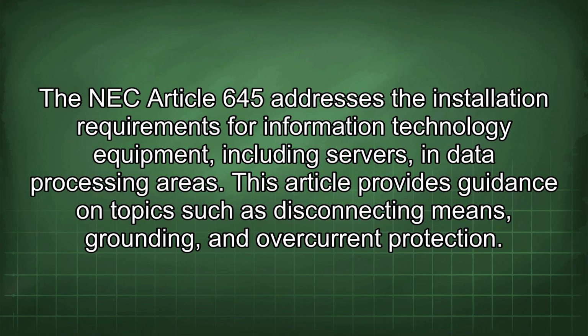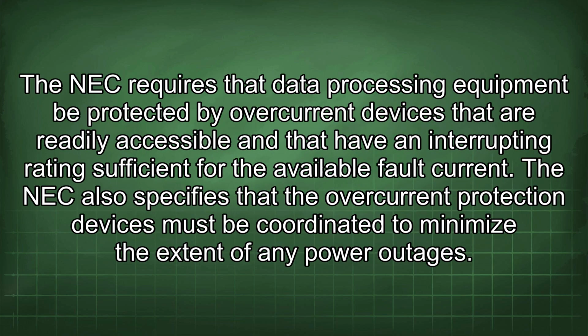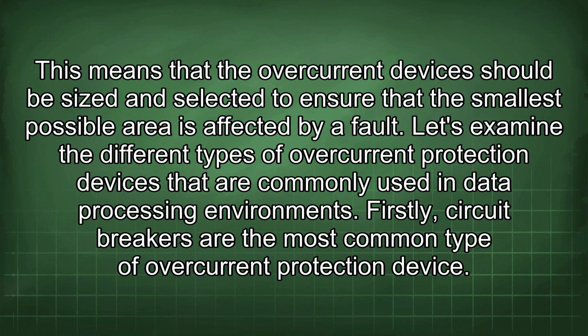This article provides guidance on topics such as disconnecting means, grounding, and overcurrent protection. The NEC requires that data processing equipment be protected by overcurrent devices that are readily accessible and that have an interrupting rating sufficient for the available fault current. The NEC also specifies that the overcurrent protection devices must be coordinated to minimize the extent of any power outages. This means that the overcurrent devices should be sized and selected to ensure that the smallest possible area is affected by a fault. Let's examine the different types of overcurrent protection devices that are commonly used in data processing environments.